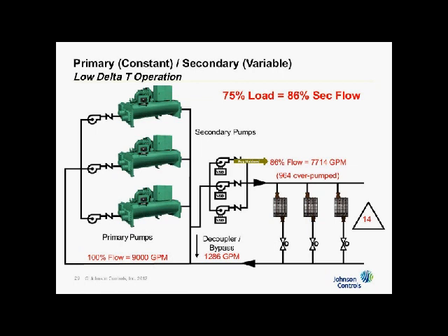Instead of having a need for 9,000 GPM, I'm pumping 75%, which is 6750 GPM. Then I've actually got 7714. So I'm over pumping 964. Okay? If I'm over pumping the 964, now I've got 1286 here and 9,000 here. Once I add the 1286 that's coming through this common, these warm up, cool down the water so that when it enters the chiller, it's at a lower yet delta T. So the chiller's just not asked to do as much. But the point that I'm trying to make here is that this doesn't match. Percent load no longer equals percent flow.